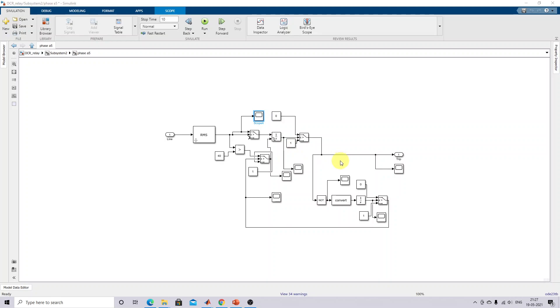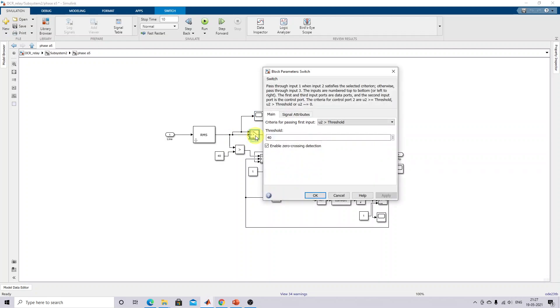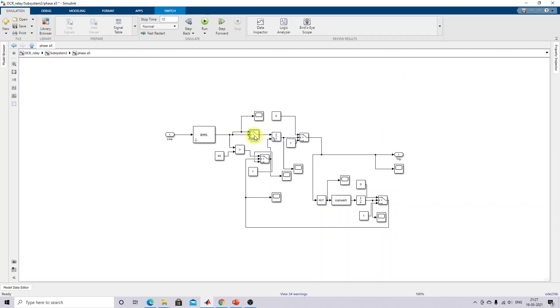You have to measure the current of any line and then find out the RMS value. This RMS value is checked against the condition — here I am using the overcurrent setting of 40 amps, checking whether the current is greater than 40 or not. Under normal condition, the current will not be beyond 40 amps; it is less than 40 amps. During that condition, the condition is false, so the output here is equal to 0.